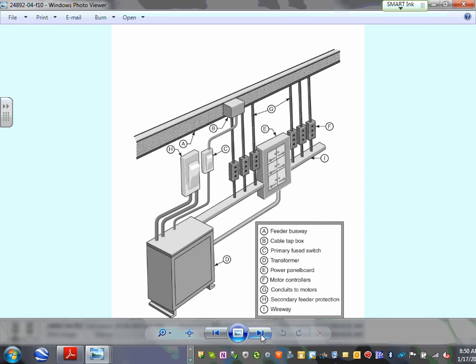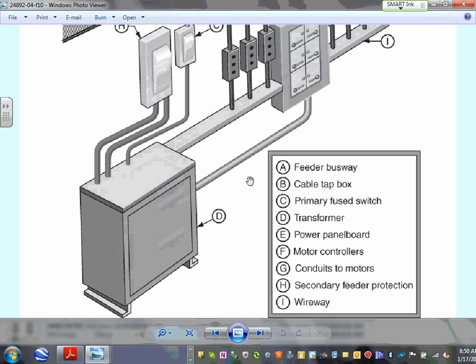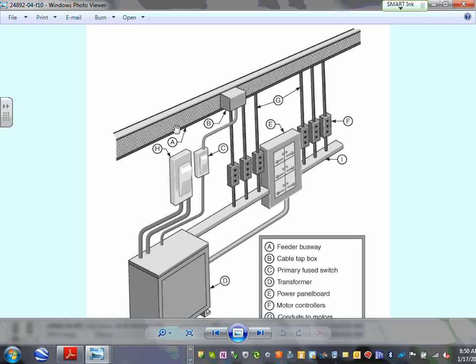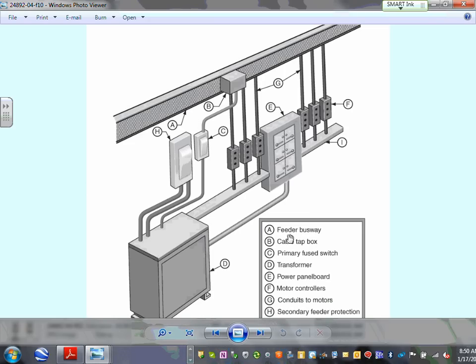We talked about fuse disconnects. This is just an arrangement that they're having, guys. Starting with A, they have a bus duct, Adam, like we did yesterday. Look at this. A bus duct, that's my bus duct, the feeder busway. They're tapping that feeder through what they call a cable tap box, and then going to the primary fuse switch. Then they came over here to a fuse switch that feeds the transformer. Then they went all the way to E, which is a panel. E is a power panel right here. From the transformer, we went into a panel, right? That's my E.